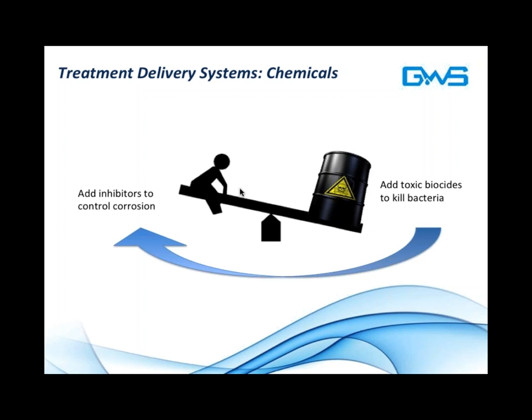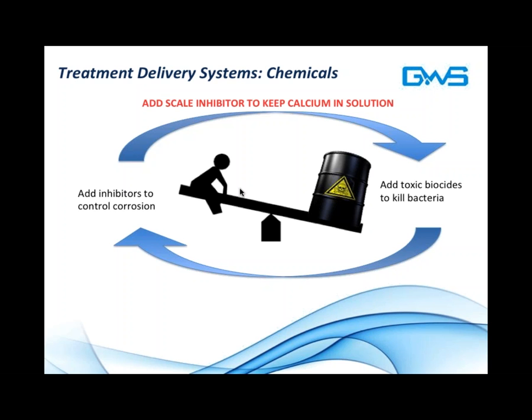So in order to compensate, chemical service partners will add inhibitors to control corrosion. The trick is that many of these corrosion inhibitors are phosphate-based, and phosphates, as you may know, are fertilizers. And fertilizers, of course, will be used to create or support biological life. So you have this back and forth between killing bacteria and adding fertilizers that grow bacteria to protect against corrosion. Meanwhile, operators have to consider scale because if they cycle the tower too high, scale will form on surfaces and complicate operation, reducing energy efficiency and heat transfer. So scale inhibitors must be added to keep calcium in solution in most cases. This process is repeated ad infinitum for the life of the tower.